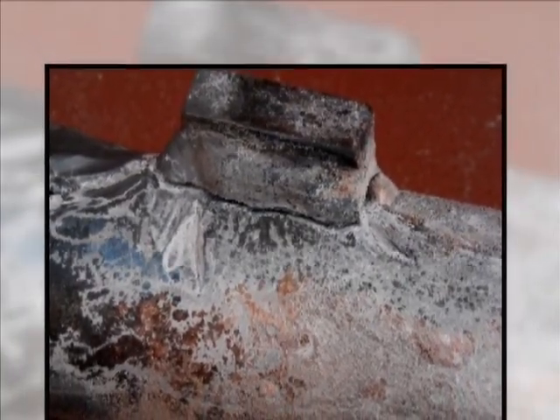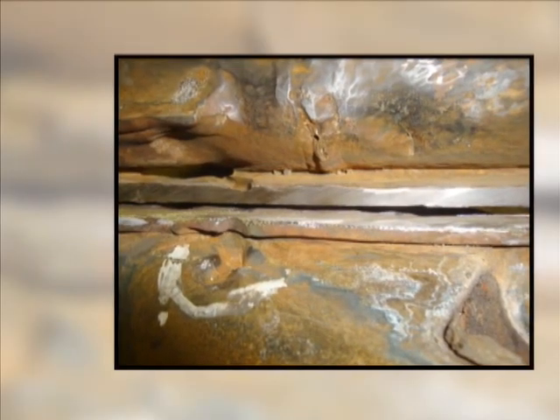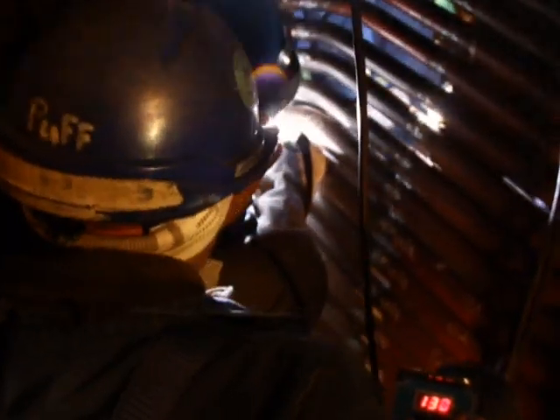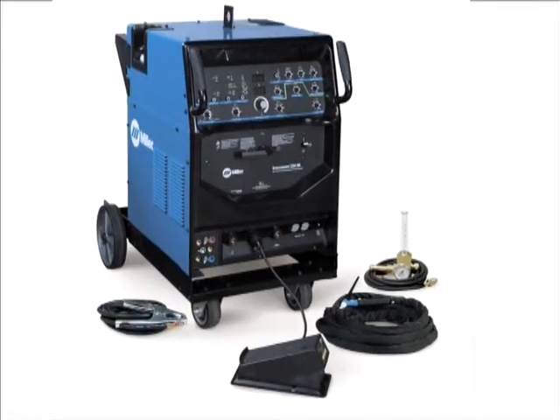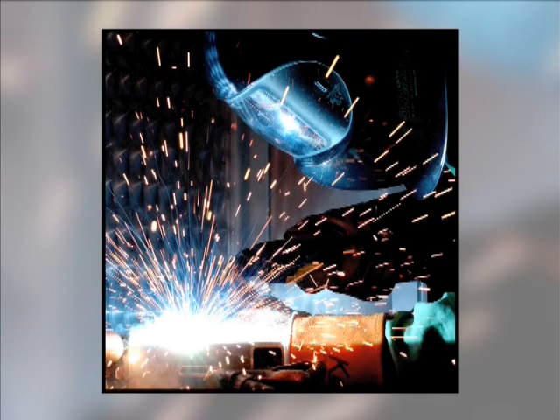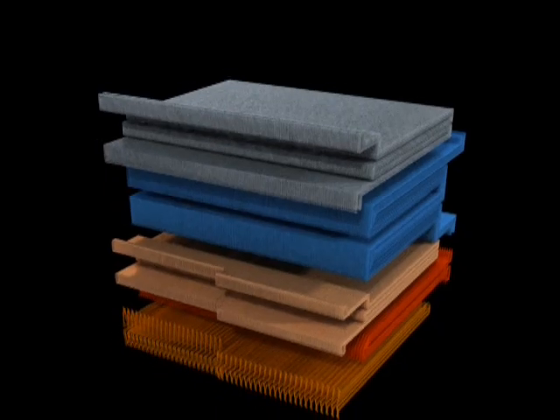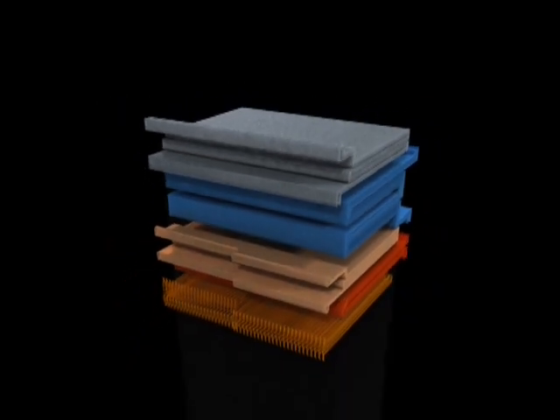There are a number of reasons why welding defects can occur, and as this list is extensive, only a few are mentioned. The skill of the welder, the control of welding consumables and equipment, poor supervision, dirty, windy, or cramped welding environment. These failures can occur anywhere in the boiler where a weld is located. Thus, there are tens of thousands of potential failure locations in each boiler.